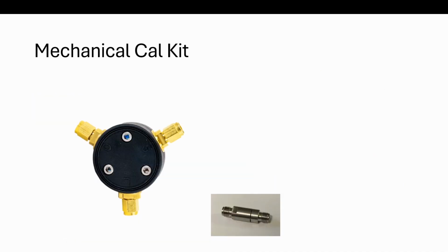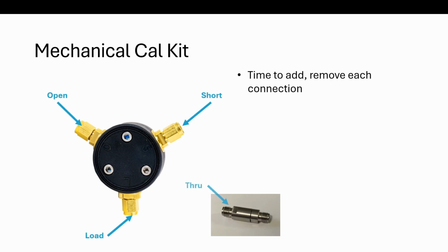While traditional calibration standards are the most widely used, they do require you to add and remove connections for each step of the measurement calibration procedure. Every connection takes time. Furthermore, connectors don't last forever even when they're of the highest quality, and after some number of insertion or connection cycles, those connectors will need to be replaced.